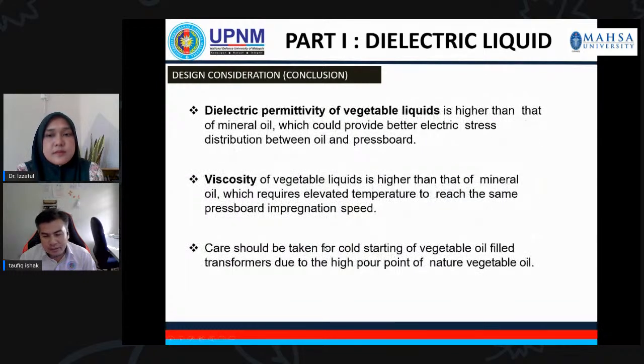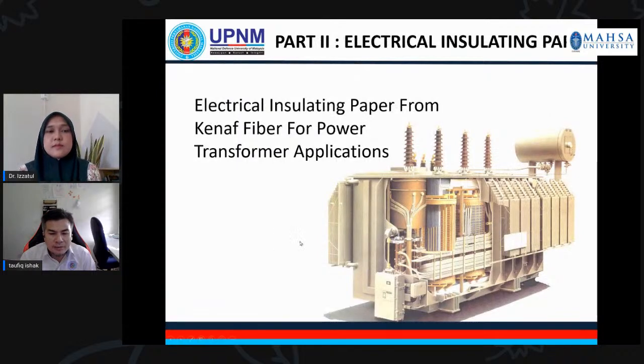In terms of dielectric permittivity, the vegetable oil is higher than the mineral oil, which could provide a better electric stress distribution between oil and pressboard. Meaning that you will have an even electric stress between oil and pressboard. In terms of viscosity, the viscosity of vegetable oil is higher than mineral oil, which requires an elevated temperature to reach the same pressboard impregnation speed. Meaning that when you use vegetable oil, you need to increase the temperature when you impregnate the pressboard, so that the speed of the impregnation process will be similar to the mineral oil.